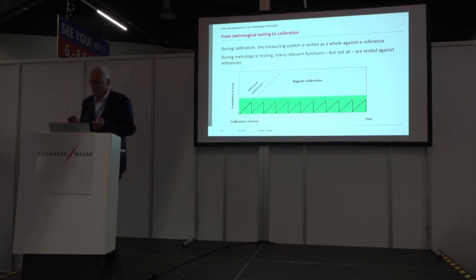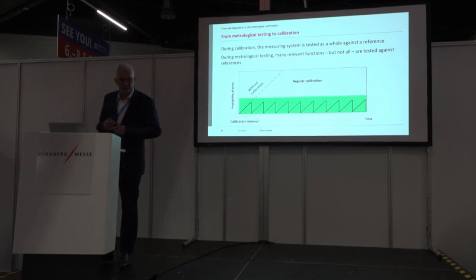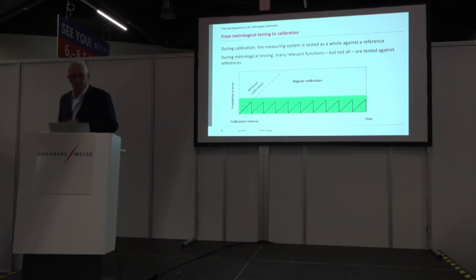You should know calibration intervals when you look at process sensors. For pH sensors, maybe 1 week, 1 month. For pressure sensors, 1 year. For flow sensors, 2 years. It depends on the sensor type. But even if you have to calibrate every year, it's difficult for these companies. It costs money, as I explained to you.